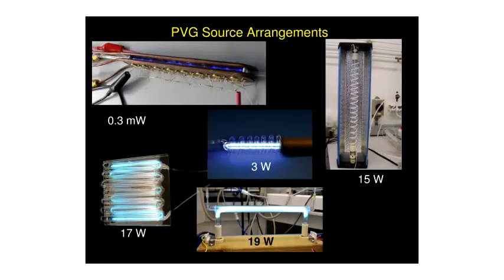A variety of UV sources can be used: from a sterilization lamp like you get from Cole-Parmer, a pen lamp used for spectroscopic alignment of instrumentation, a flow-through lamp, even light-emitting diodes — very low power LEDs operating in the deep UV.